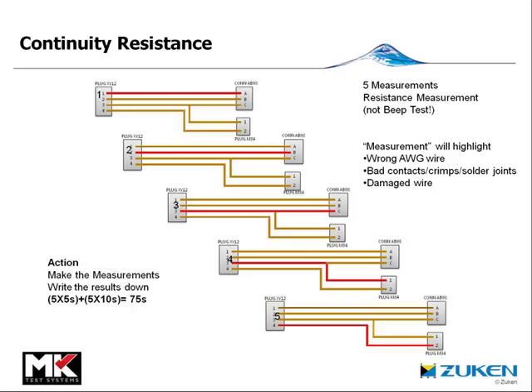The very least that we want to do to test this harness is continuity resistance measurement, short circuit test, and high voltage test. For the continuity resistance measurement on this simple harness, we have 5 measurements to make. Allowing a bare minimum of 5 seconds to make each measurement and 10 seconds to log the results, that is 75 seconds of manual testing. Measurement is key, as it highlights the nature of any failure such as wrong wire gauge, bad crimps, solders, or damaged wires.